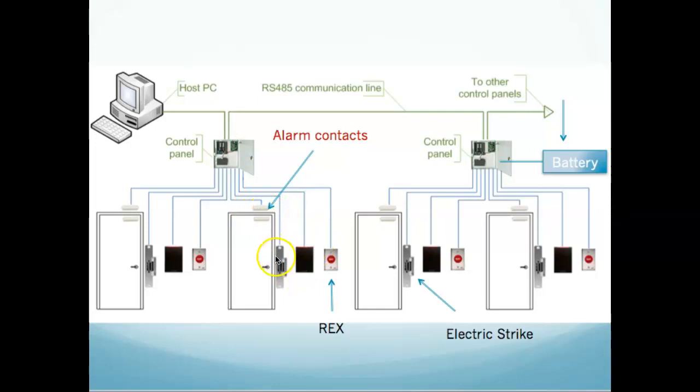Now, if I don't use my card on this card access reader, and instead use a crowbar to open the door, this signal goes up and says, hey, these two sensors just separated. The alarm contacts, the door sensors, the reed switches just separated. And there is no valid entry or exit using a REX device we talked about. So send the alarm to the host and tell them something's wrong at that door.